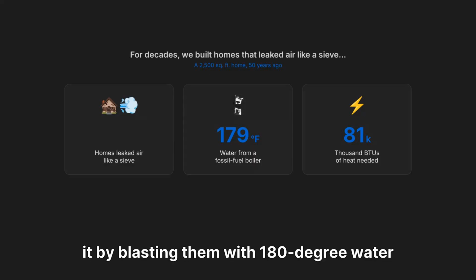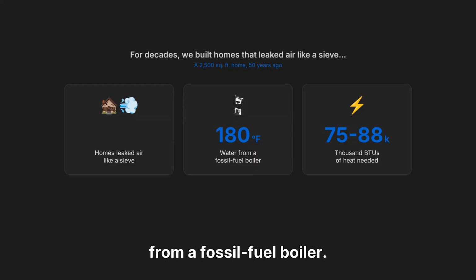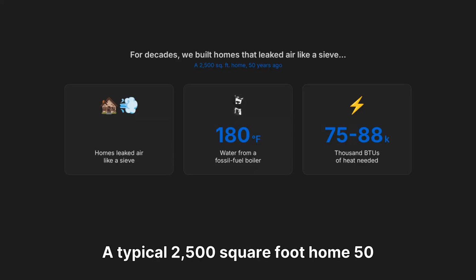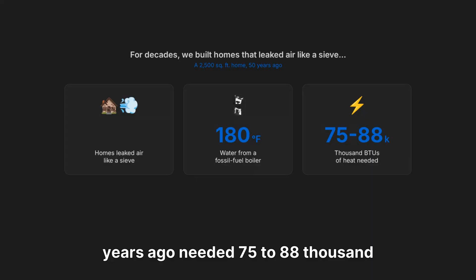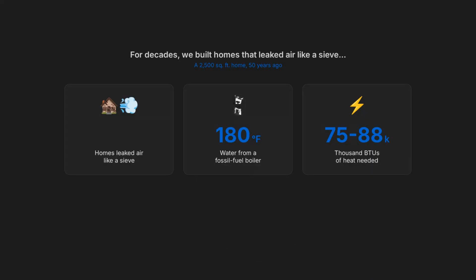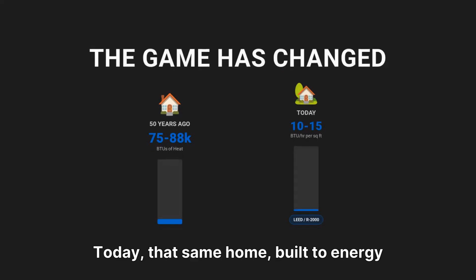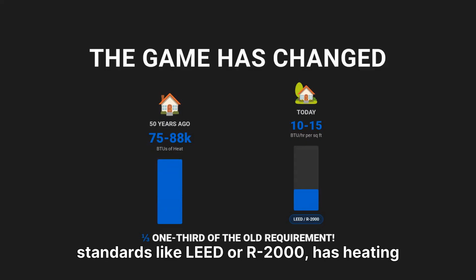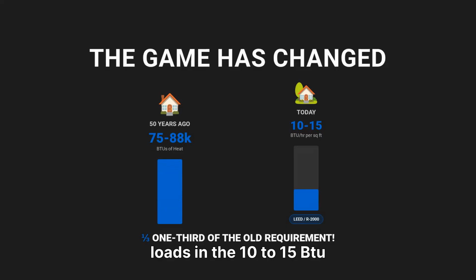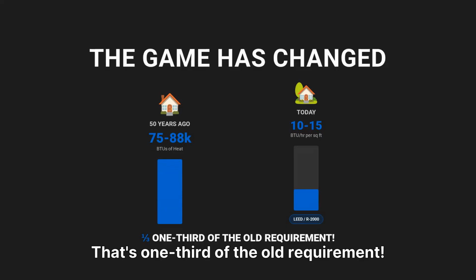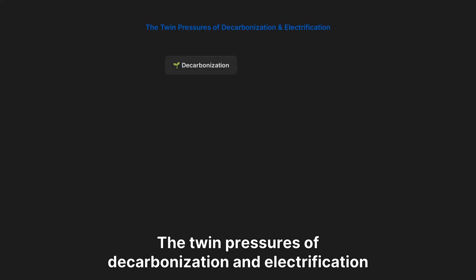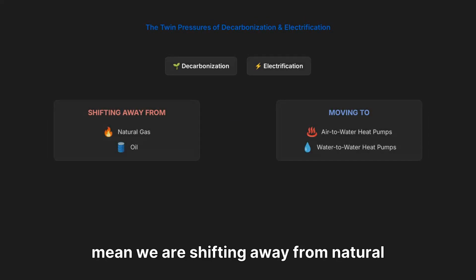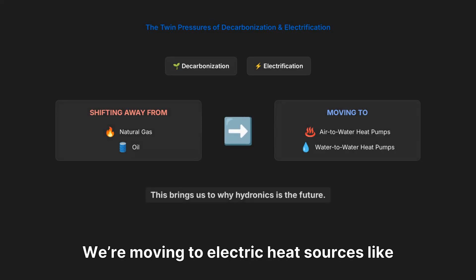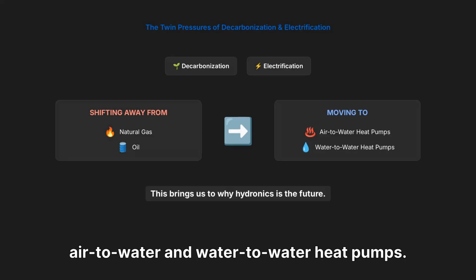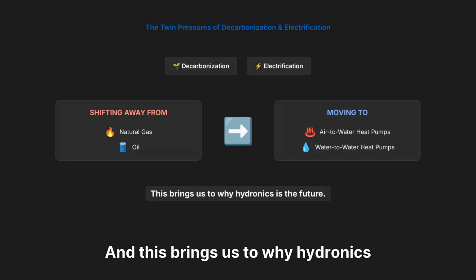For decades, we built homes that leaked air like a sieve, and we solved it by blasting them with 180-degree water from a fossil fuel boiler. A typical 2,500 square foot home 50 years ago needed 75 to 88,000 BTUs of heat. The game has changed. Today, that same home, built to energy standards like LEED or R-2000, has heating loads in the 10 to 15 BTU per hour per square foot range. That's 1/3 of the old requirement. The twin pressures of decarbonization and electrification mean we are shifting away from natural gas and oil. We're moving to electric heat sources like air-to-water and water-to-water heat pumps. And this brings us to why hydronics is the future.